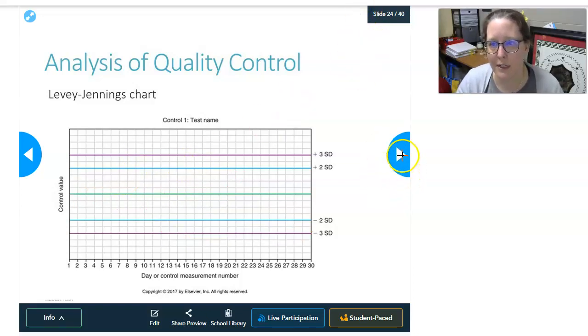So that gives you an idea of what's going on there. So these Levey-Jennings charts can be viewed on the analyzers for every test, every level of quality control, and usually for more than 30 days. Usually however long you've been running, you can view these charts. And so this allows you to analyze and see what's going on with your test, and it can help you make decisions on how to resolve what's going on.